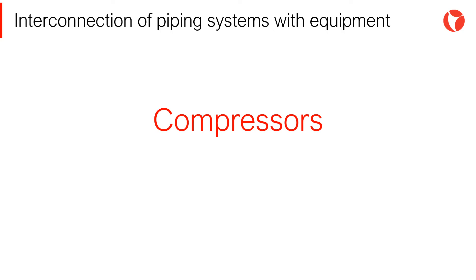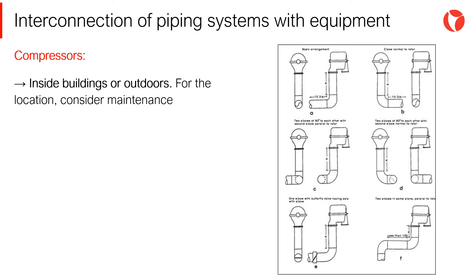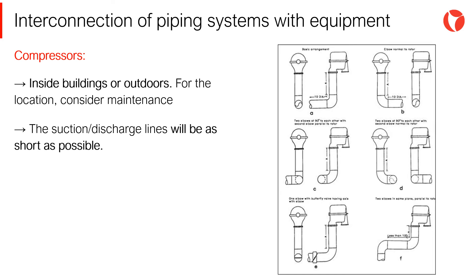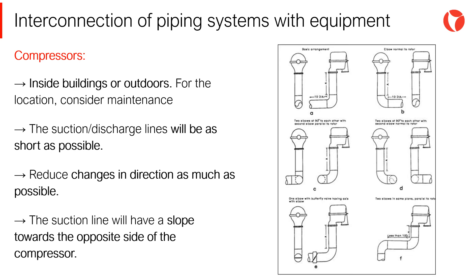The interconnection of compressors is very complex, mainly due to the fact that they are very sensitive to loads and changes in the boundary conditions. An inadequate design results in equipment failure and outage in a very short period of time. Generally, compressors can be located inside buildings or outdoors, depending mainly on maintenance requirements. The compressor suction and discharge lines should be as short as possible, with the least amount of direction changes. The suction line will slope towards the opposite side to the compressor.